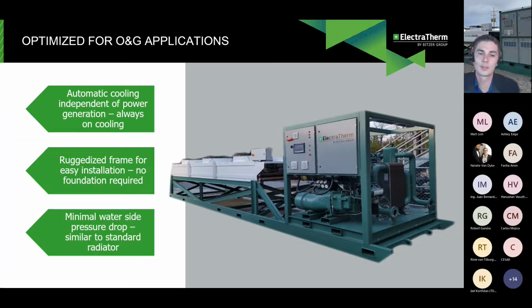Now, we have optimized this system for oil and gas applications. I really like this photo because you can see the hot water supply and return to the right side of the photograph and the very robust ruggedized sled. That also serves a purpose for easing installation, so there's no significant foundation requirements for that. And it's automatic cooling independent of power generation, as mentioned previously. We've designed the system to have minimal water side pressure drop, so it's designed to be exactly similar to a radiator, in the sense that you can use standard pumps. Typically in most applications, you wouldn't have to upgrade.